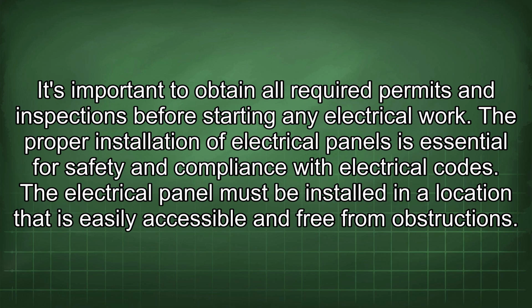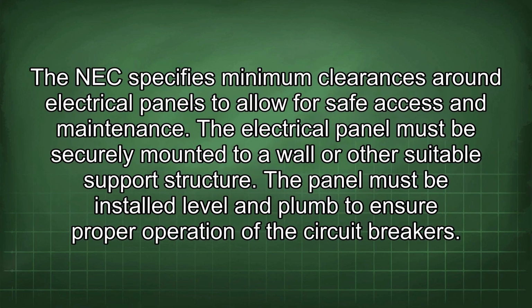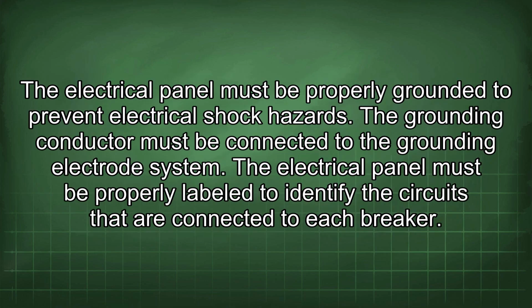The proper installation of electrical panels is essential for safety and compliance with electrical codes. The electrical panel must be installed in a location that is easily accessible and free from obstruction. The NEC specifies minimum clearances around electrical panels to allow for safe access and maintenance. The electrical panel must be securely mounted to a wall or other suitable support structure. A panel must be installed level and plumb to ensure proper operation of the circuit breakers. The electrical panel must be properly grounded to prevent electrical shock hazards. The grounding conductor must be connected to the grounding electrode system.